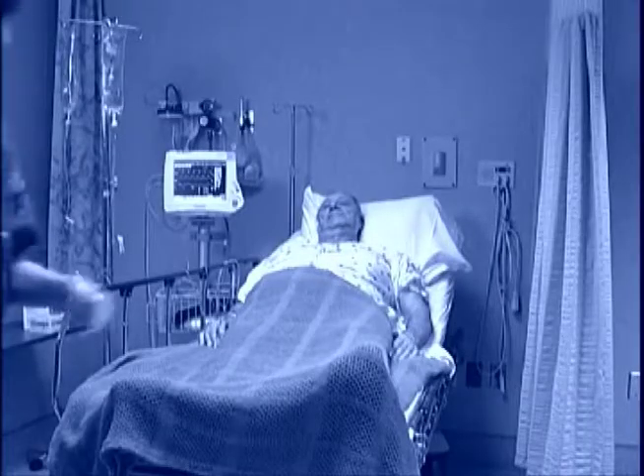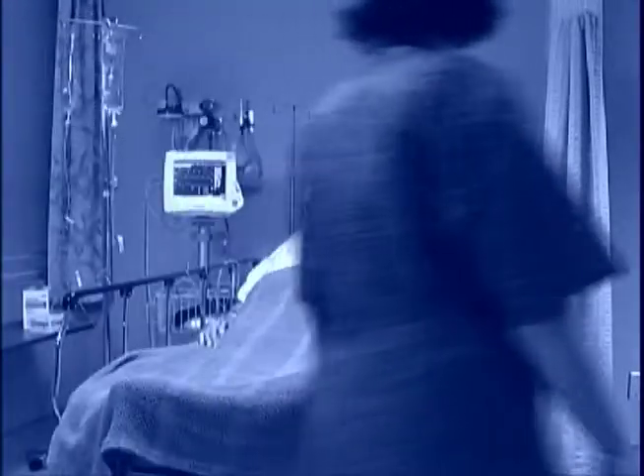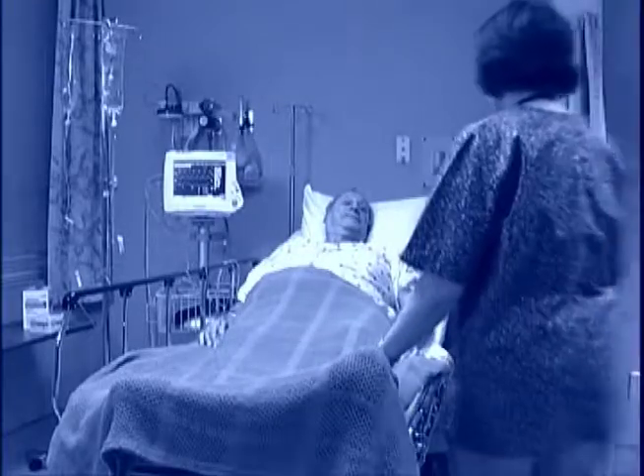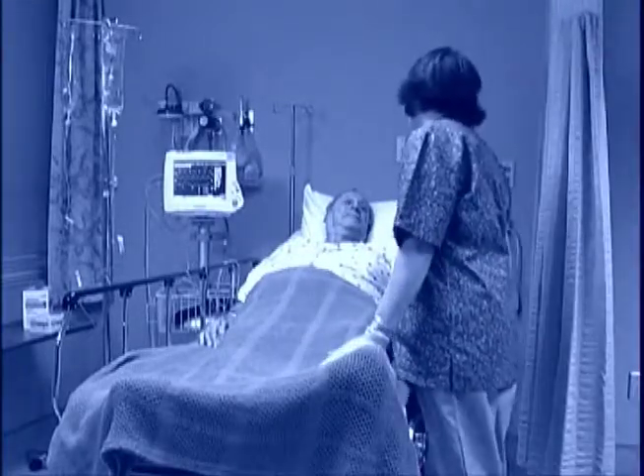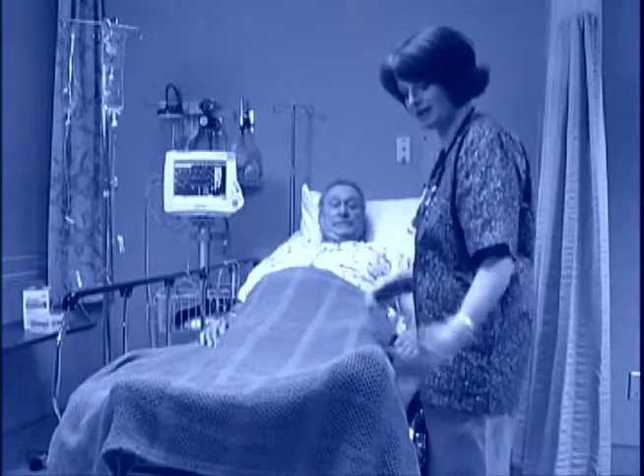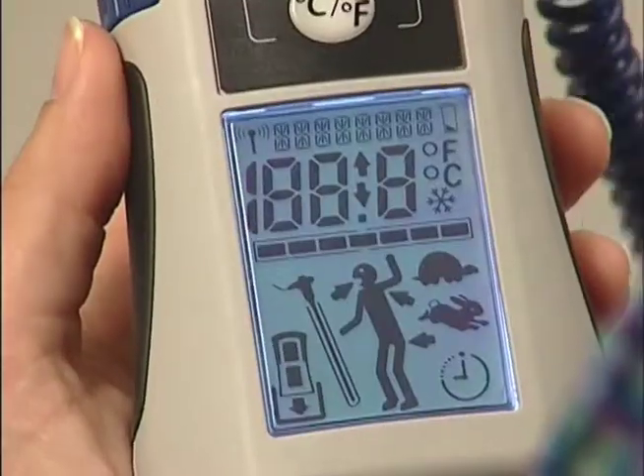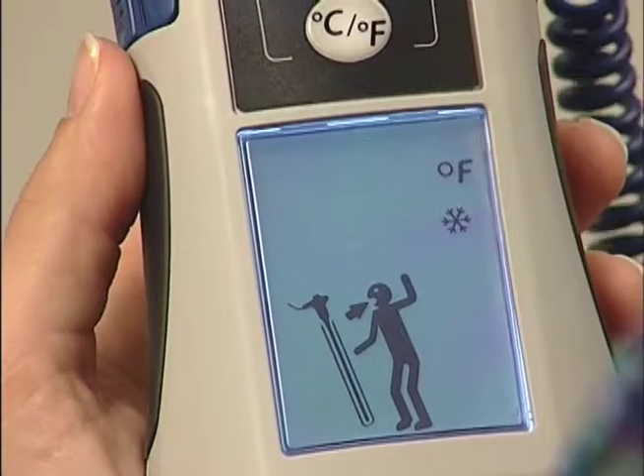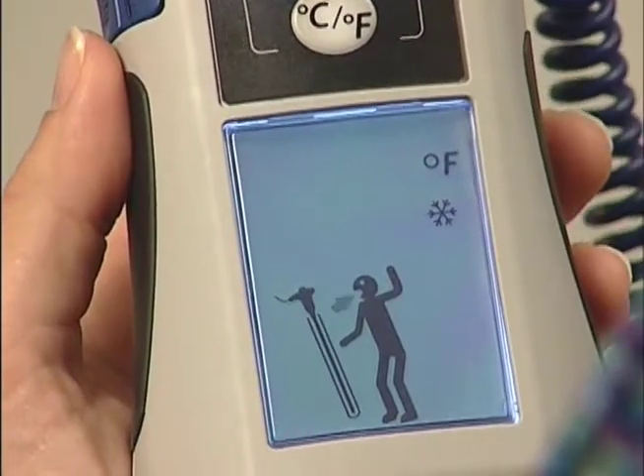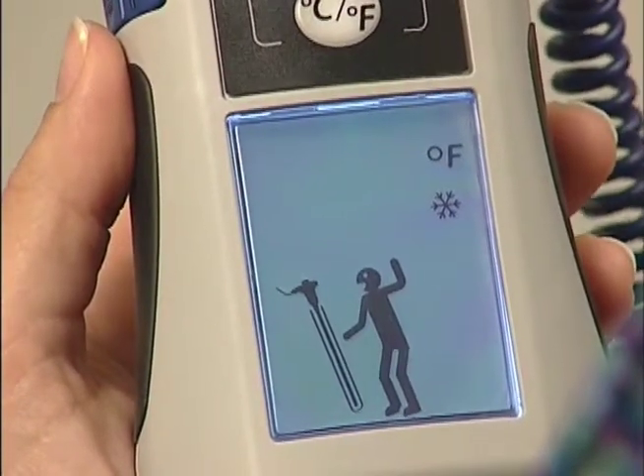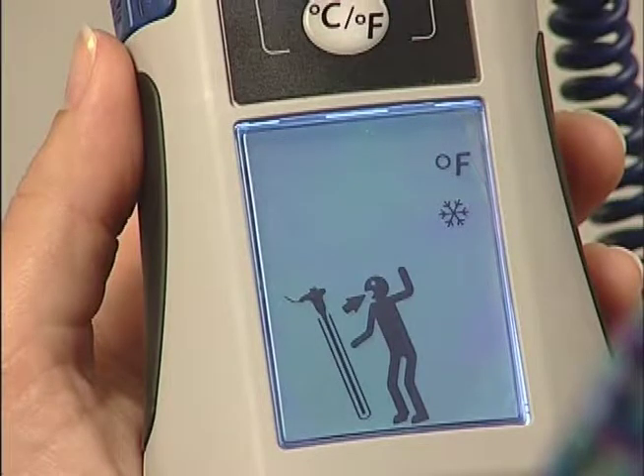The Filac Advanced may be set to operate in cold mode. Cold mode is provided for use in applications where body temperatures may be lower than normal, such as for patients recently out of surgery. When selected, a snowflake icon will appear on the front panel display. In cold mode, the probe preheats to 91 degrees Fahrenheit, 33 degrees Celsius. All other functions remain the same.